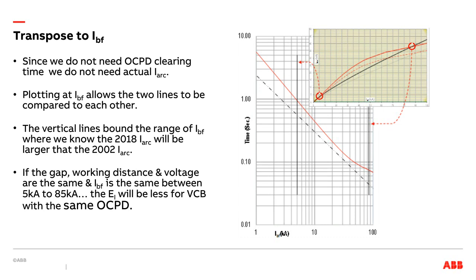That also helps you now within this region between these 2 black lines. This data is comparable because you can assume time is the same, gap is the same, working distance is the same, enclosure is the same. The only thing that's different is VCB old versus VCB new, incident energy old versus incident energy new. All the other variables are essentially held steady.